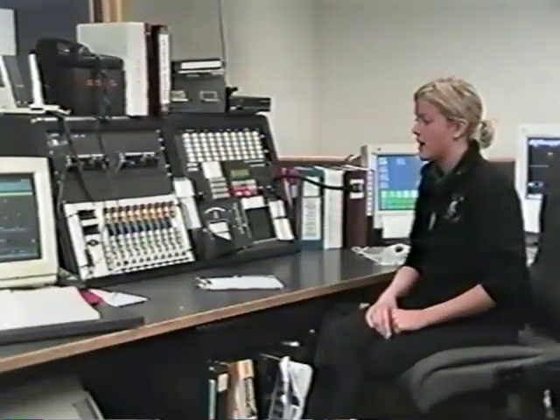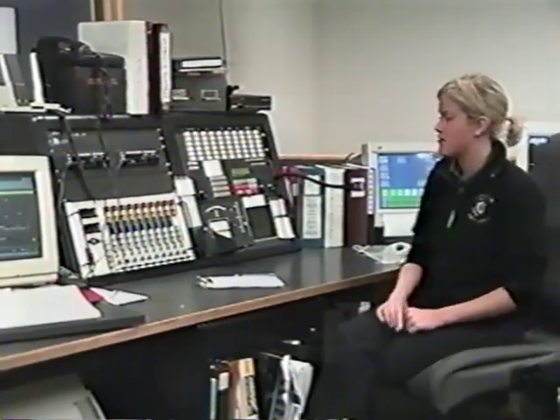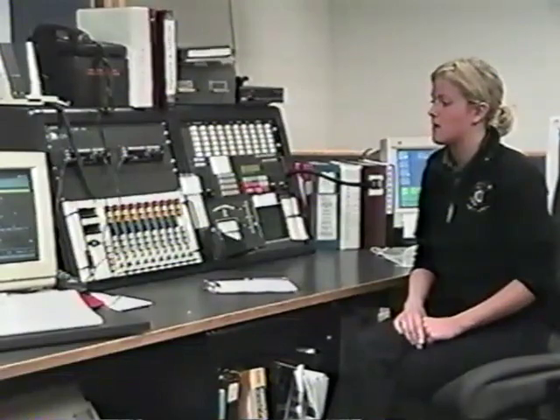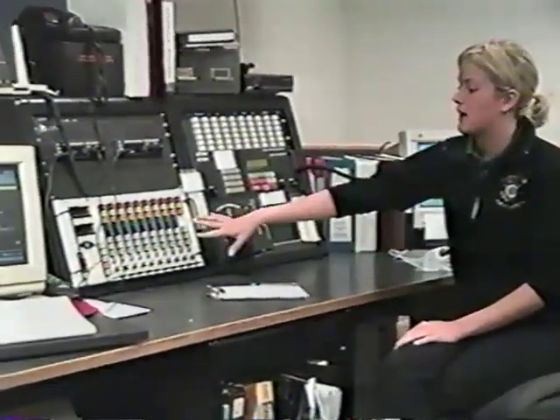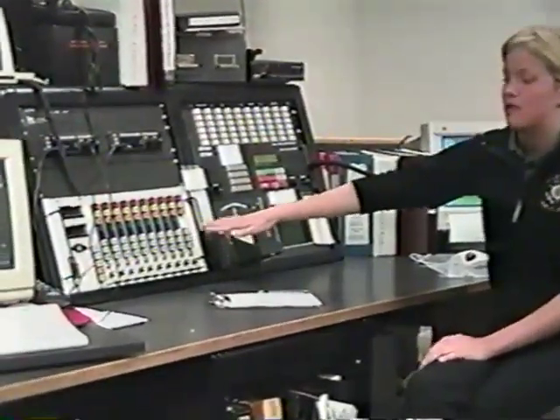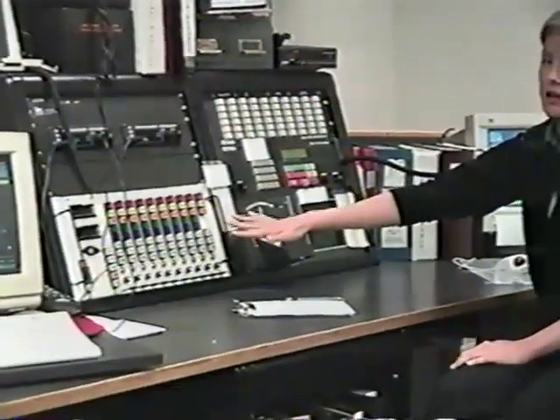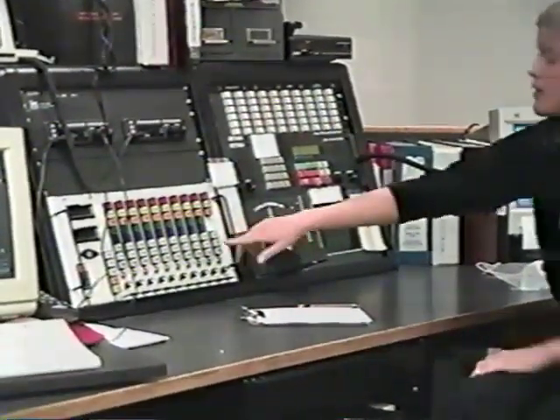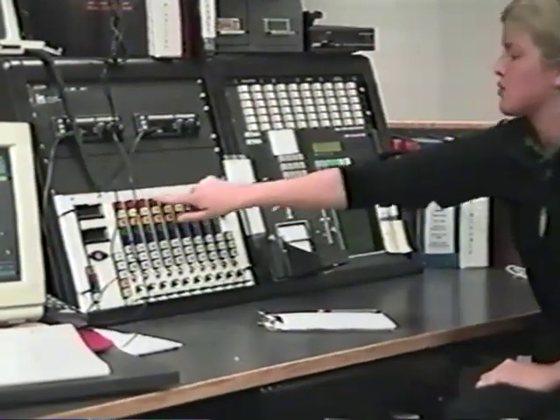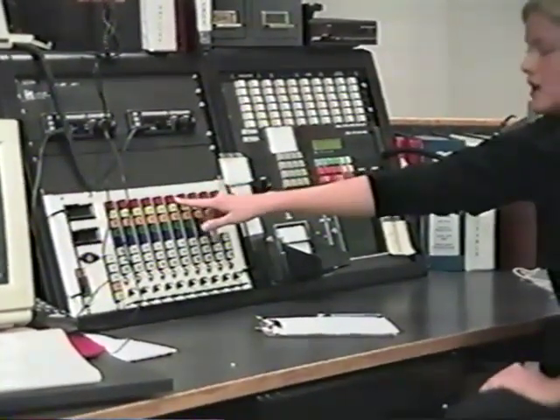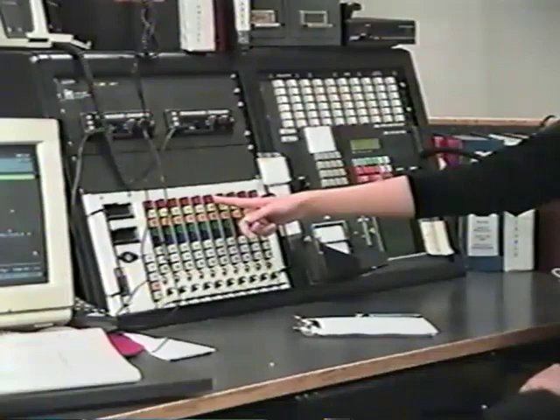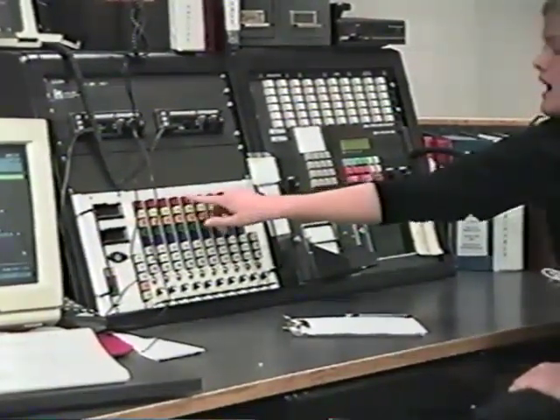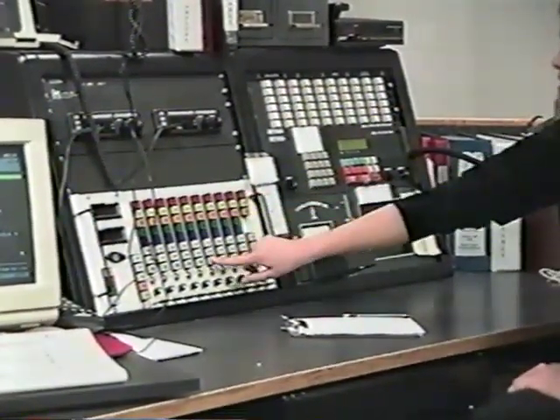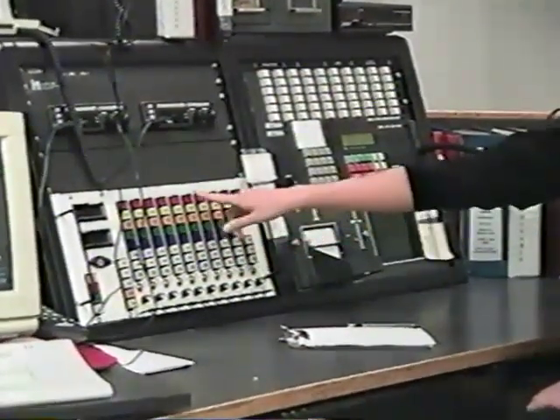I'm going to be going over the difference between a master box, a Keltron alarm, and also what an open circuit is. First of all, a master box alarm is basically an alarm that comes in over this panel here that lets us know that there may be a fire happening somewhere in town. There are a bunch of different circuits. We have circuits 1 through 6 that are actually connected to lines in town, and they depict different areas of town. For instance, circuit number 6 covers all of Ballardvale Street.